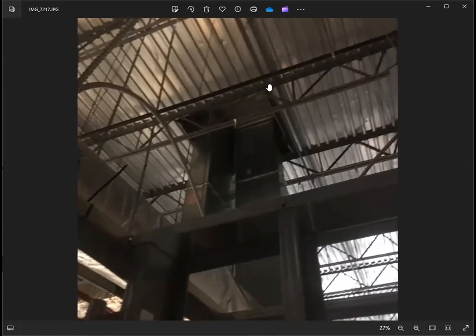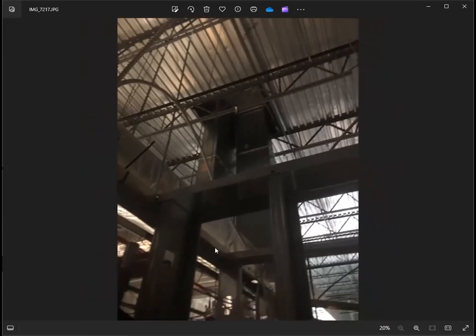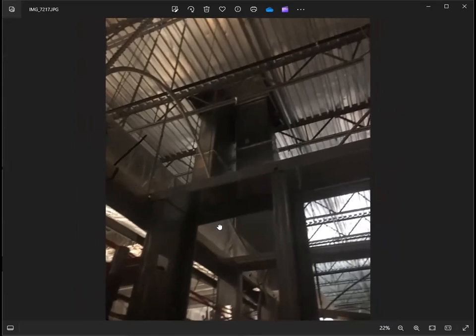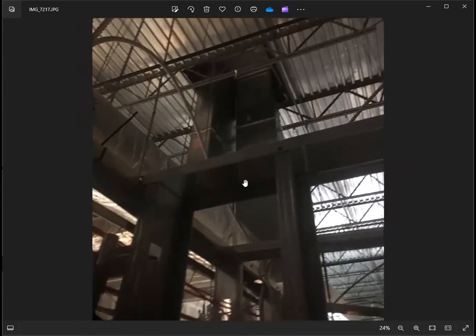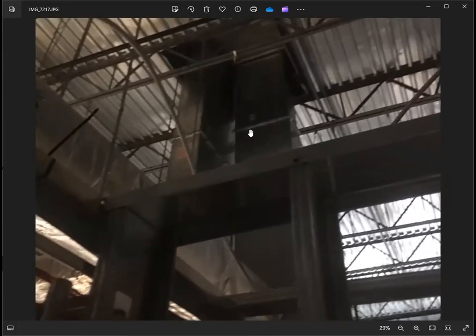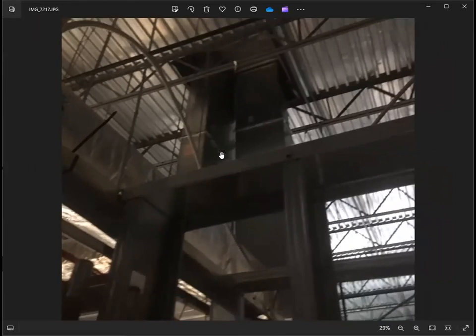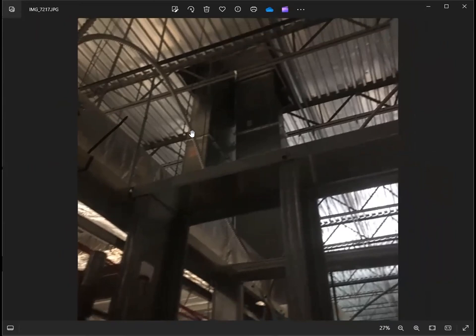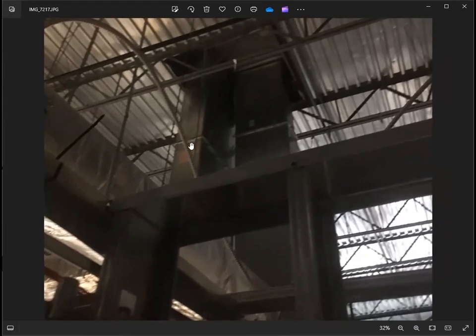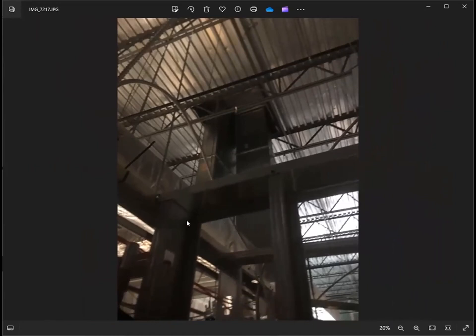So the rooftop unit is what you call, one of the definitions is, economizers. And you can see the ductwork here. It's insulated but the riser was not. So in this case, either the ductwork is existing and it has an existing liner of insulation inside. That's what you call a liner when it's insulated inside. So the new horizontal ductwork hanging on top of the drop ceiling is insulated.